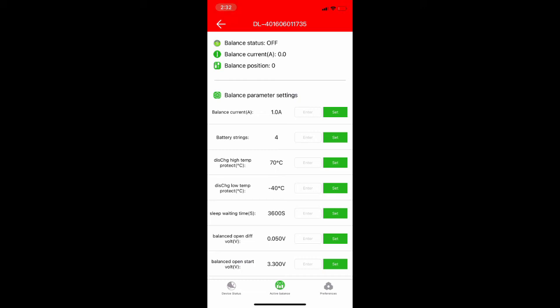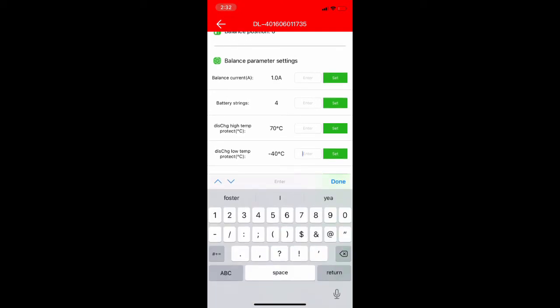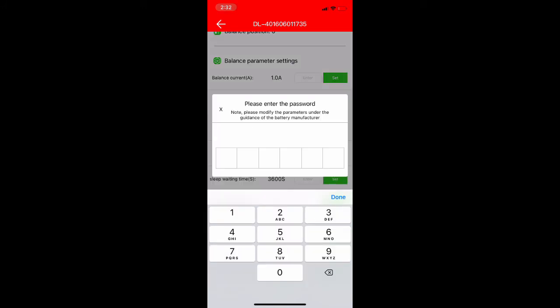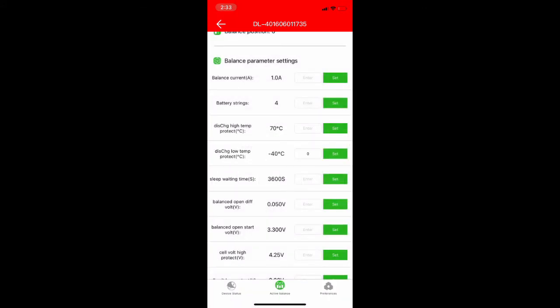The discharge high temp protect is currently sitting at 70 degrees - I don't see any reason to change that. The discharge low temp is currently set to -40, so we'll change that to 0. The password is the same as the rest, just 123456, then hit set, and you'll notice it updates in a second or two.